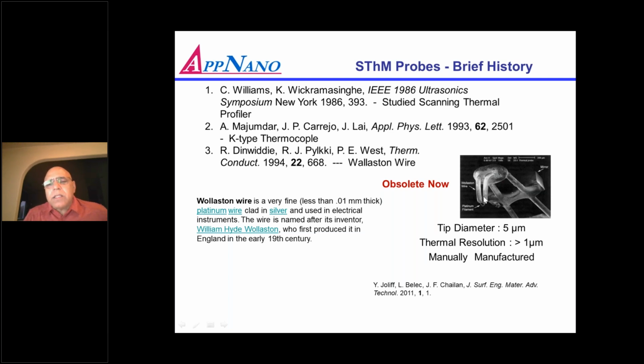The good part was this probe added so much in the STHM inventions. People were using this probe even for heating purposes, because this thermocouple is very robust, so you can heat it also, not very high, but you can heat and get a very good thermal conductivity contrast. The big problem was the resolution, and that was one of the bottlenecks. As the size of the features was shrinking, this probe could not keep pace with the technology, so it has now become obsolete and nobody is making those.